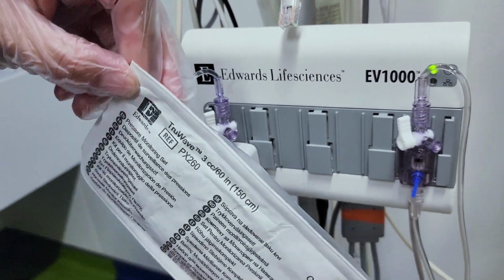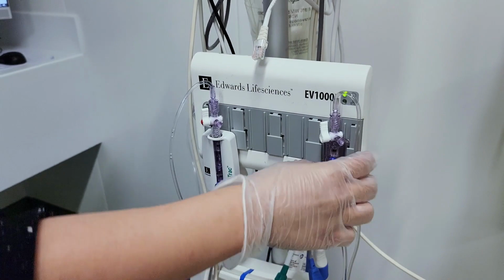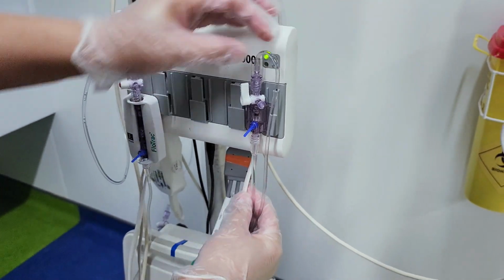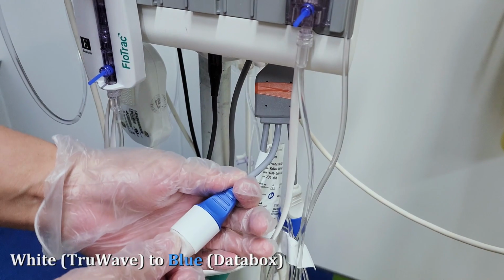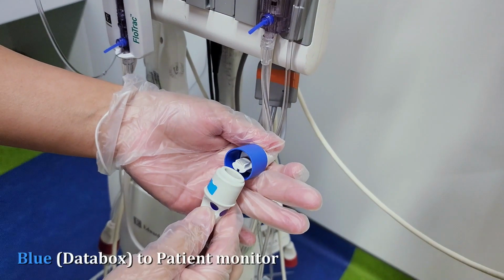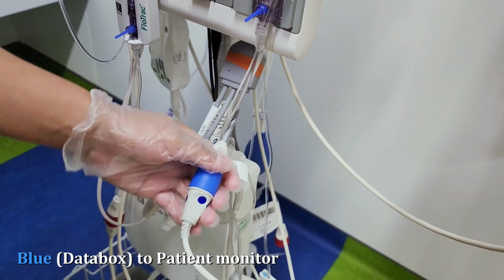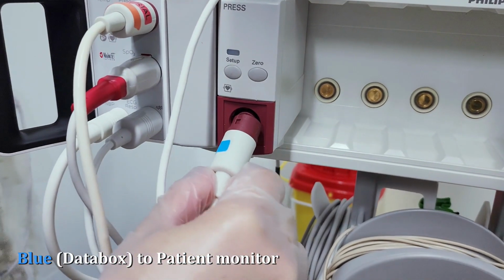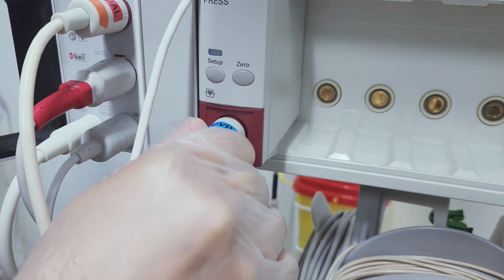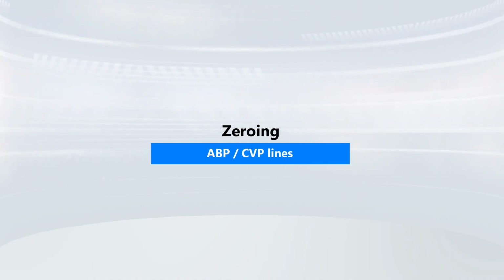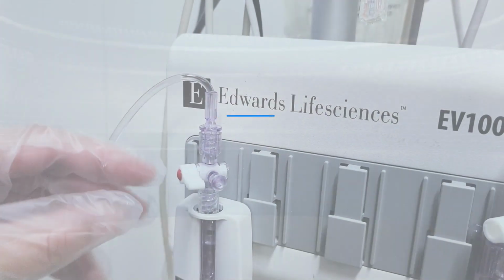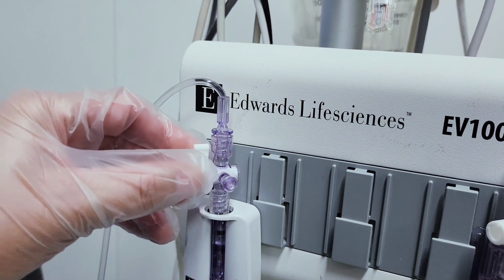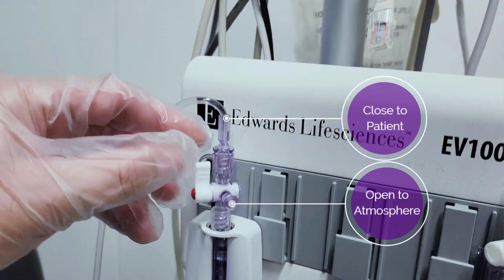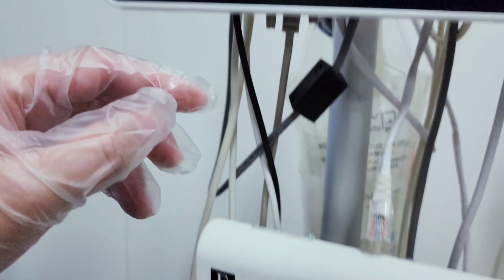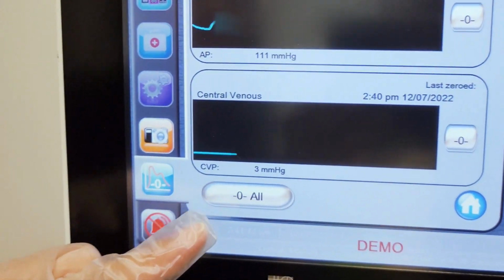The TruWave sensor has a white cable end and should be connected to the color blue connection of the data box. And the blue cable end of the data box should be connected to the patient's monitor for CVP reading. To do the zeroing, turn the stopcock off to the patient and open to atmospheric air. Touch the zeroing button for arterial channel, then press home.